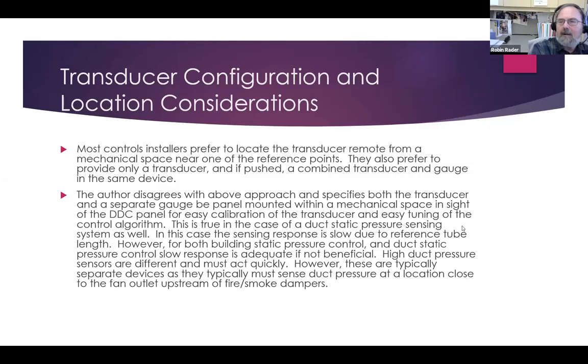And I do this with duct static as well. I like to have the transducer in the mechanical room. The duct static pressure tube is long in that case, and the sensing of static pressure has a fairly large lag, but in my opinion, that's fine. I don't see a problem with it. High duct static pressure sensors are different though. They need to act quickly, and so you need to have a short sensor in that case.